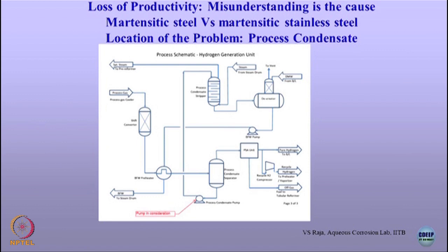That water is more corrosive than the water you have in the pipelines. It is a pure water. Okay. You see why later. And they got worried. You know what they did? They started using two pumps alternatively, one or the other, right? I said, why do you use them alternatively? Because any time it will go, and if I order a new pump with martensitic stainless steel, it may take not less than 6 months. Without this pump, the whole unit cannot run.